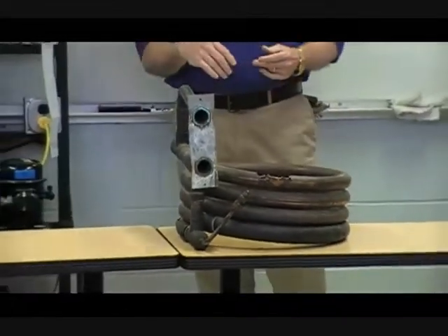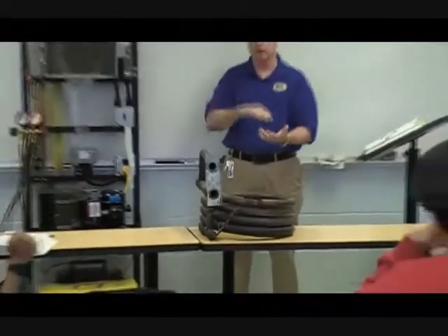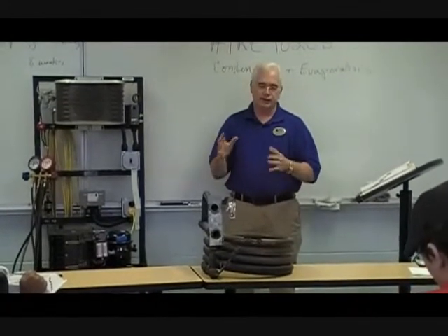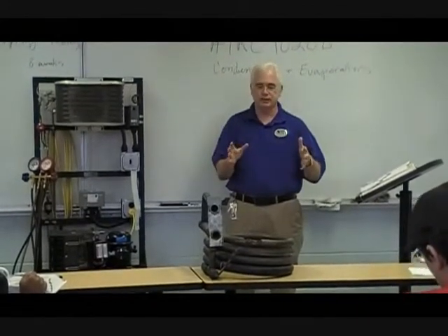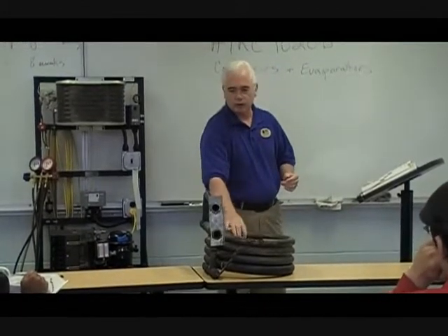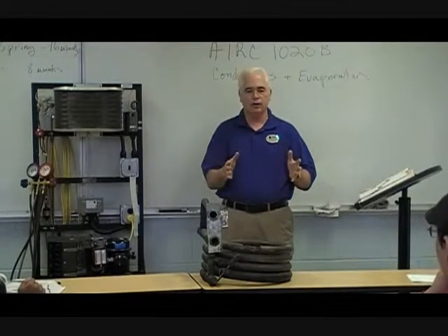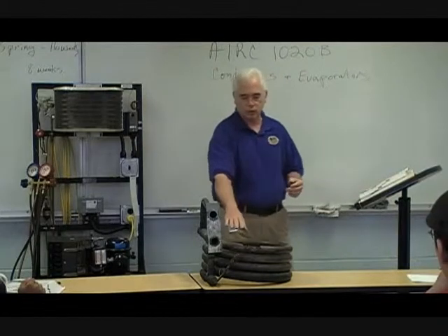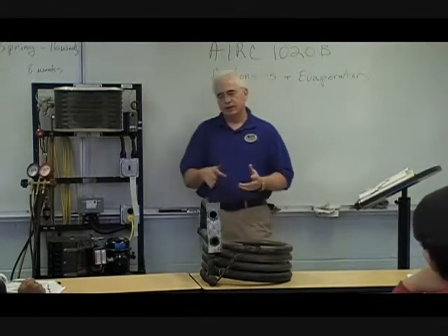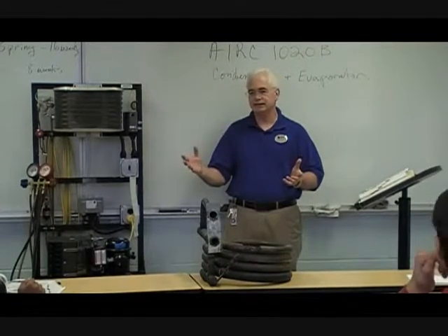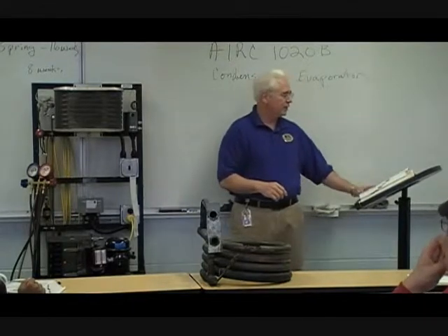Water source heat pumps are pretty popular. Typically, you have an air coil and a water coil. In the cooling mode, the air coil is the evaporator and the water coil is your condenser. If the unit is in the heating mode, the air coil becomes your condenser and the water coil becomes your evaporator. But keep in mind, the condenser does what? Rejects heat, and the evaporator absorbs heat. So when you understand what the condenser does, you can recognize the part that it plays in the system, and you know what it's supposed to do.